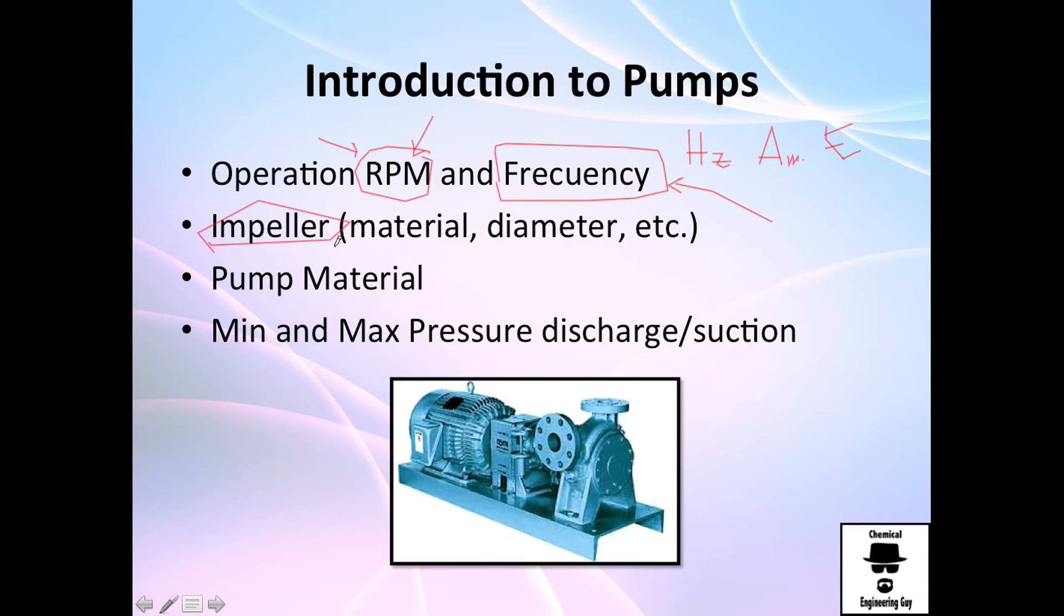The impeller, what type of material. Is it steel or is it iron, what's being used. The diameter is what's important, the size, the angle, all those. The shape of the impeller is very important. Pump material as well and the minimum and maximum discharge and suction pressure. So what is the minimum operation pressure right here and the maximum operation right here. Is it suitable for your operation or even for your pipe? Is it safe or is it not safe? You need to check out that as well.